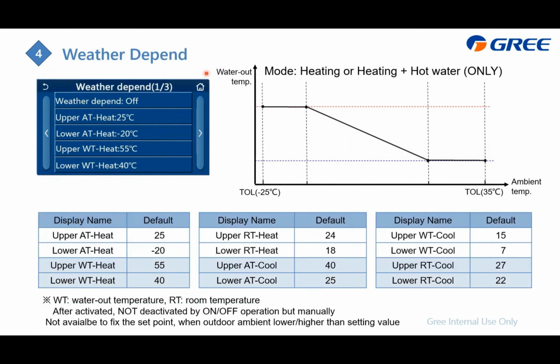Weather depend mode. For this one, according to your preset, the preset items include the outdoor ambient temperature upper limit and lower limit, and also for heating or cooling, the upper limit and lower limit. And the target you can select to be the WT, that means the water out temperature, and the RT, that means the room temperature. And the system will, according to the detected real-time outdoor ambient temperature, decide the target temperature.